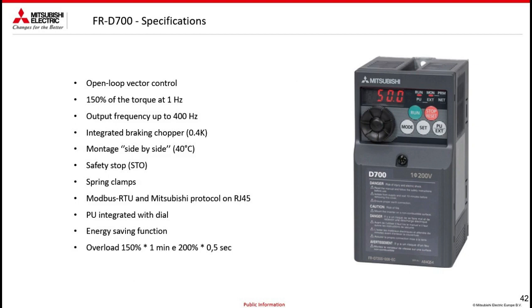The FRD700 inverter has several highly appreciated features, such as open loop vector control, which allows you to obtain 150% of the torque at 1 Hz, which would be unthinkable for a three-phase asynchronous motor in V/F control, because it has low voltages at low frequencies, and since the torque is also given by the square of the voltage, I could have a low torque value. Output frequency up to 400 Hz, compared to the nominal frequency of a motor which is on the order of 50 Hz. Integrated braking chopper from 400 watts upwards, to dissipate any excess energy, because below that it is not possible to move excessive inertial loads.